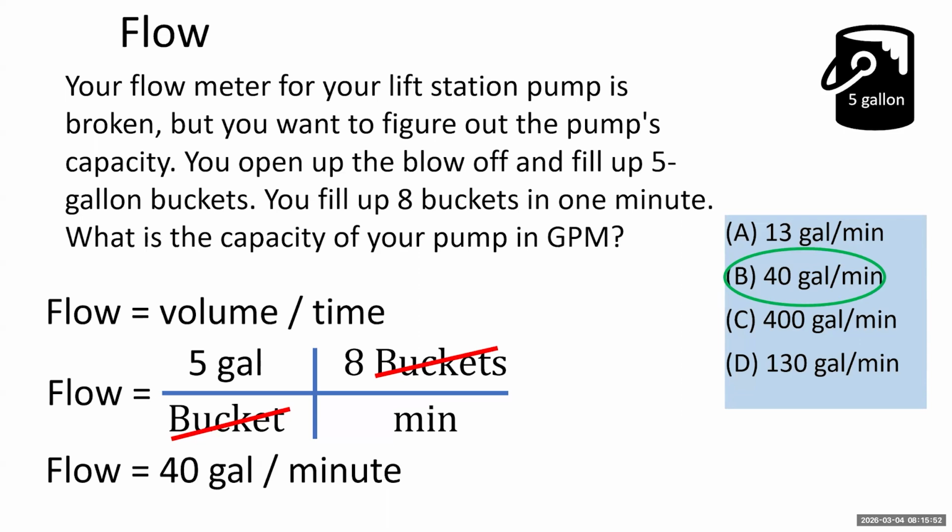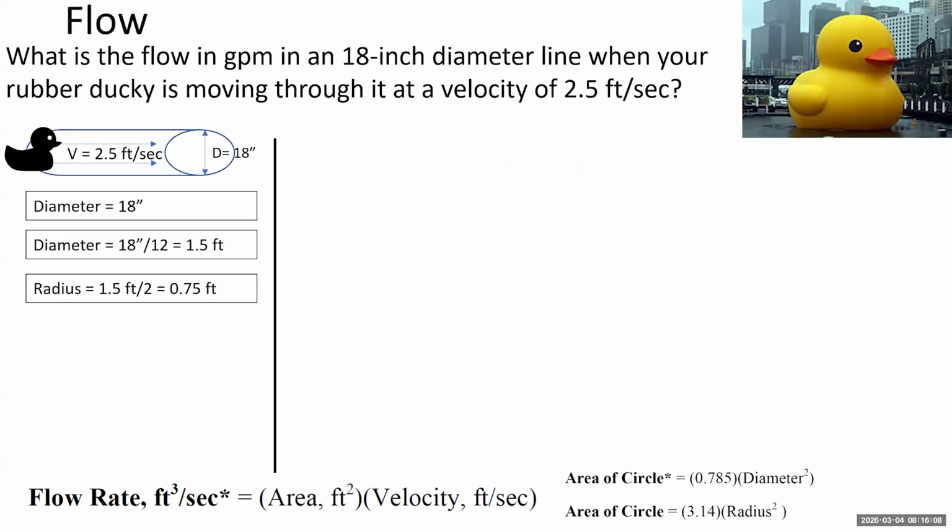So that's a concept of flow, but this is probably not the type of question you're going to see on an exam. But we want to share this with you because this is really what flow is all about. How much water in how much time, right? So here's a question that you're more likely to see on an exam. What is the flow in gallons per minute in an 18-inch diameter line when your rubber ducky is moving through it at a velocity of 2.5 feet per second? The test probably won't talk about your rubber ducky, but it will probably give you the velocity.